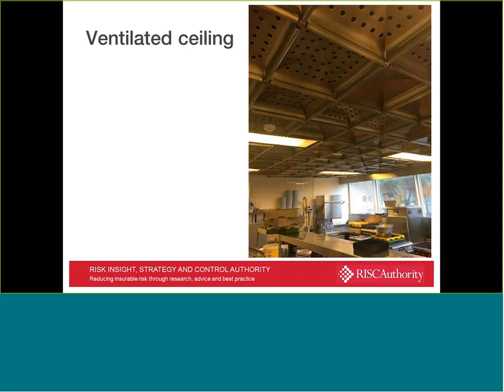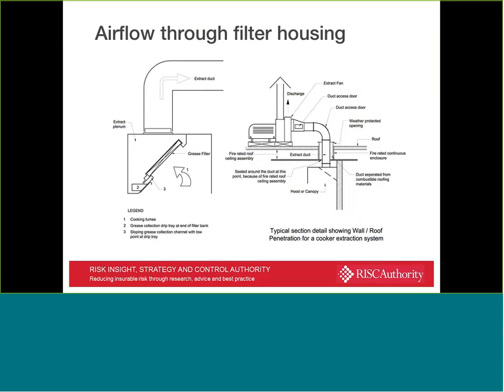Manufacturers insist that they're designed to stop grease and fats falling back down into the kitchen environment, but whether or not they're as hygienic as other types of system, I don't really know. But in terms of the hood itself and the systems themselves, regardless of the type of extract that exists, they're really there for three functions. They're there to provide a degree of fire protection, in as much as they're there to remove grease from the environment and present it in a way that can be easily cleaned. They're also there to remove smoke and heat and vapor, and to provide more appropriate working conditions for those who are based in that environment. So it's not just about the fire safety element. They're also there to serve other purposes.